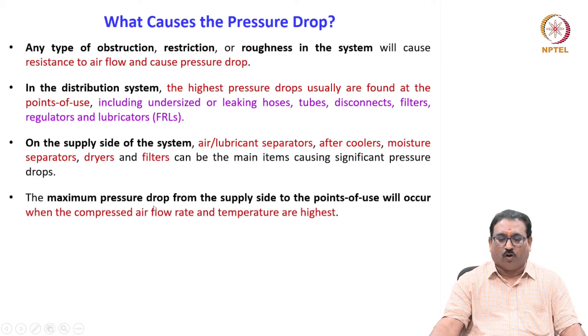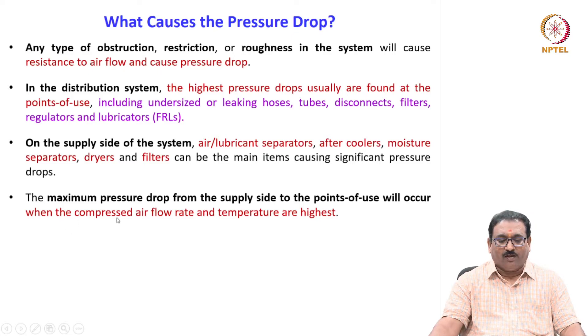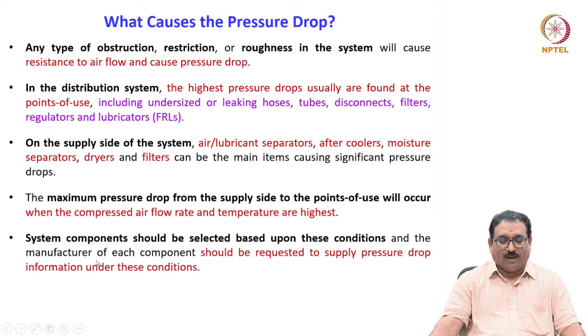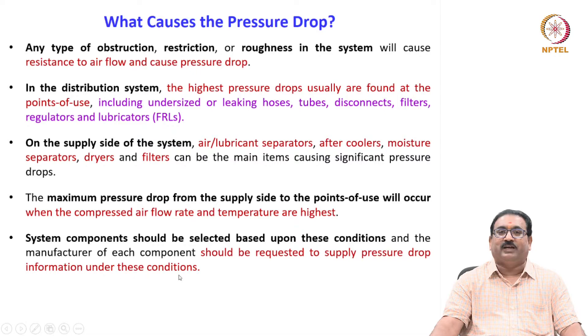The maximum pressure drop from the supply side to the point of use will occur when the compressed air flow rate and temperature are highest. System components should be selected based upon these conditions, and the manufacturer of each component should be requested to supply the pressure drop information under these conditions.